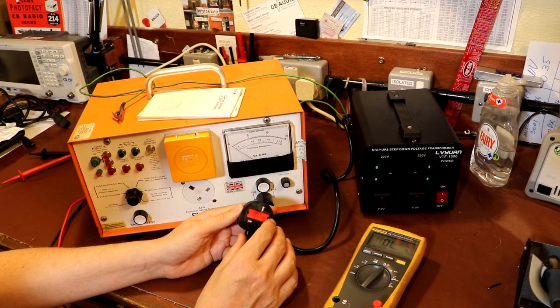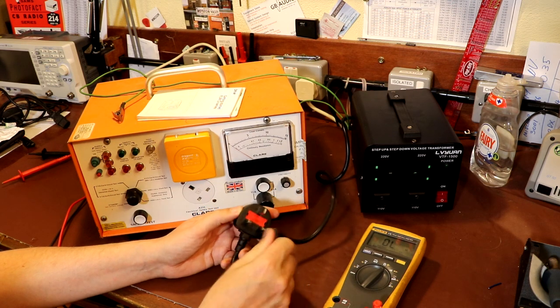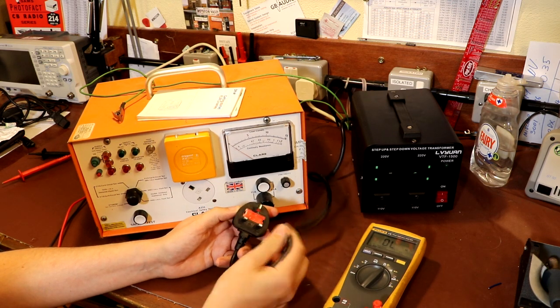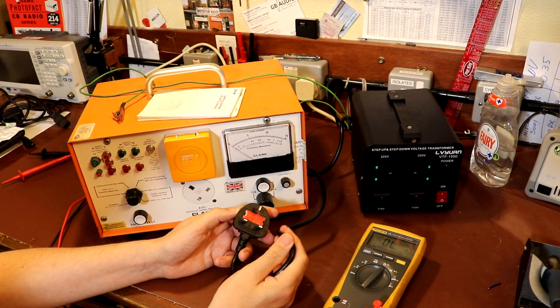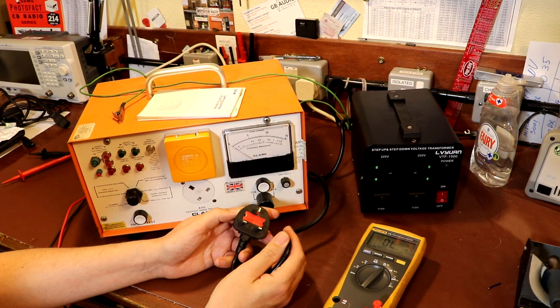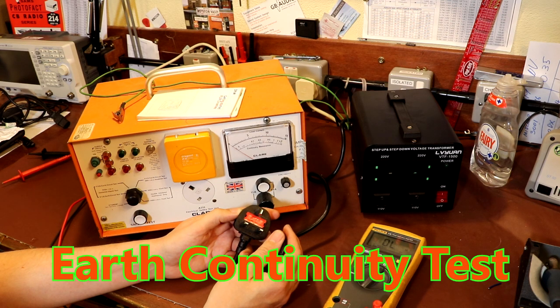The other thing we're going to do is see how good the earth bonding is on the piece of equipment. So we want to make sure that if there is a fault inside and a live wire touches the case, the wiring here is suitably rated so that the fault will go to ground and it will trip out the main circuit breaker and disconnect the device. So we're also going to do this earth impedance test as well.